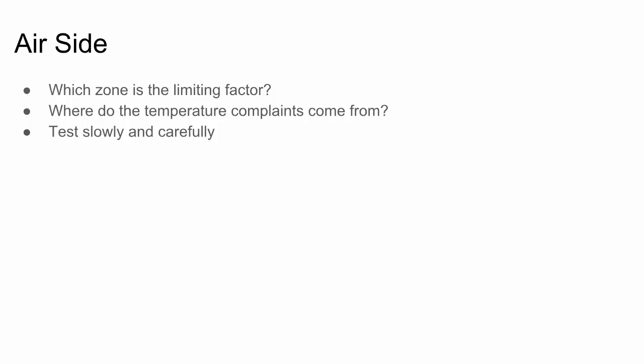So keeping with the example of the air handlers, we can increase the supply air temperature set point of a given air handler and see how it responds. If we find that we're able to make that increase and the zone is still well served and the people are happy and the equipment's not overheating, then that may be a sustainable change. And we really want to do this slowly and carefully. So we're not going to make that change, look at it for half an hour and assume it's okay. We want to observe that over time and really be patient and go slowly with this stuff and convince ourselves that we really can increase that supply temperature set point and leave it like that permanently and still have a good performance in that zone.